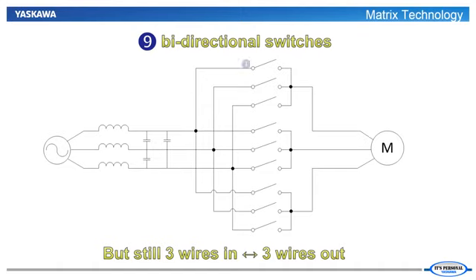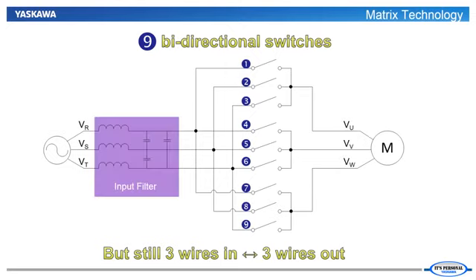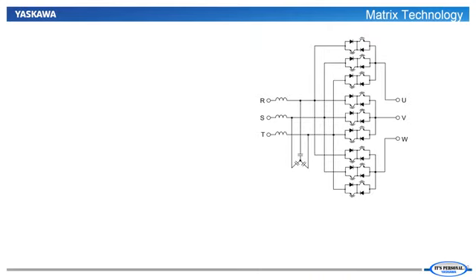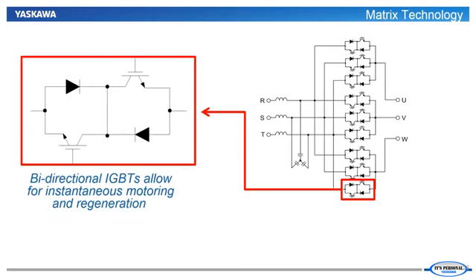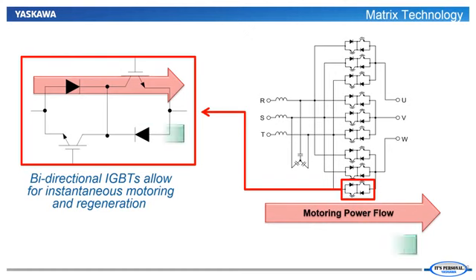The power section of the matrix is dominated by 9 bidirectional switches. The 9 switches are required because we need to be able to connect any of the 3 input phases to any of the 3 output phases. Also included in the power section is an input filter. The input filter is necessary to filter out the pulse width modulation of any regenerated power going back to the power supply. Let's take a closer look at the 9 switches. By using the bidirectional switches, the matrix drive has the ability to allow motoring or regenerative power flow.